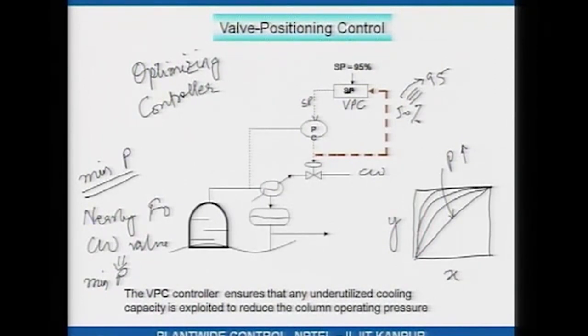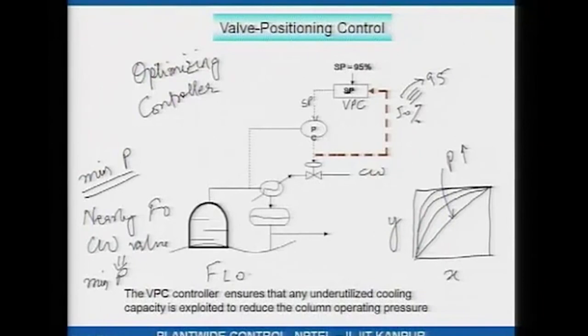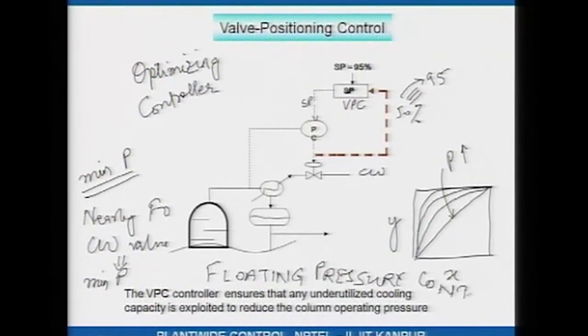What the valve positioning controller is essentially doing is saying: my cooling water valve is not fully open, which means I can reduce the pressure of the column. When I reduce the pressure set point, the pressure controller opens the cooling water valve, and slowly but surely the cooling water valve approaches nearly fully open, meaning the column is operating at as low a pressure as possible. This is also sometimes referred to as floating pressure control. Let me give another example of a valve positioning controller.